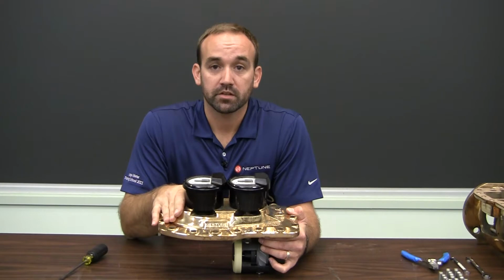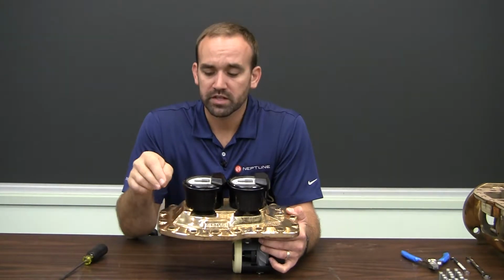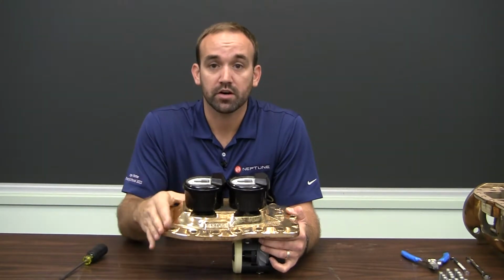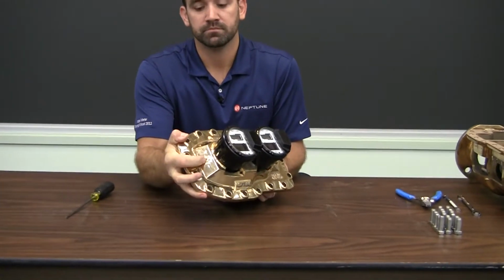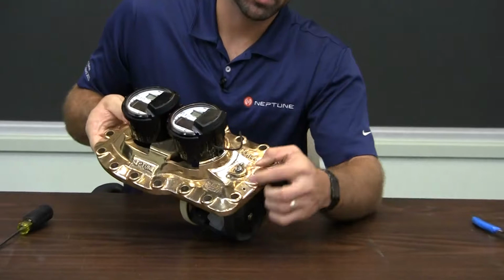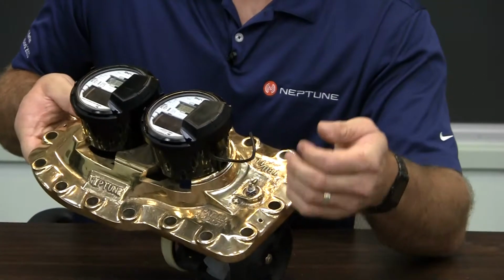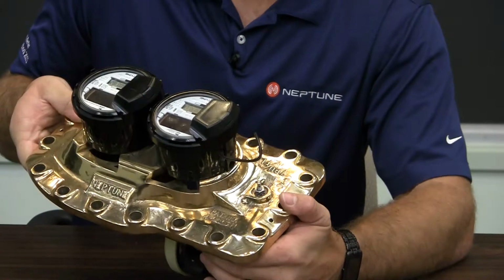Before we break down the cover assembly, I think it's important to mention a few of the traits here on the main case. Cast in, you can see a directional arrow. You can also see the calibration vane and a plus and a minus letting you know which way to calibrate the meter, up or down.